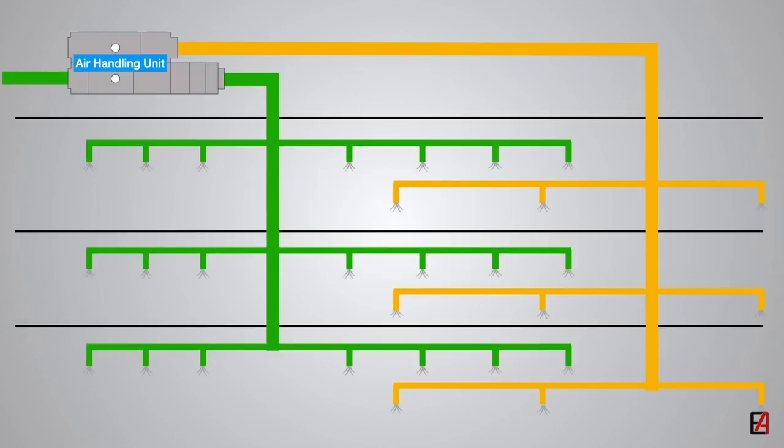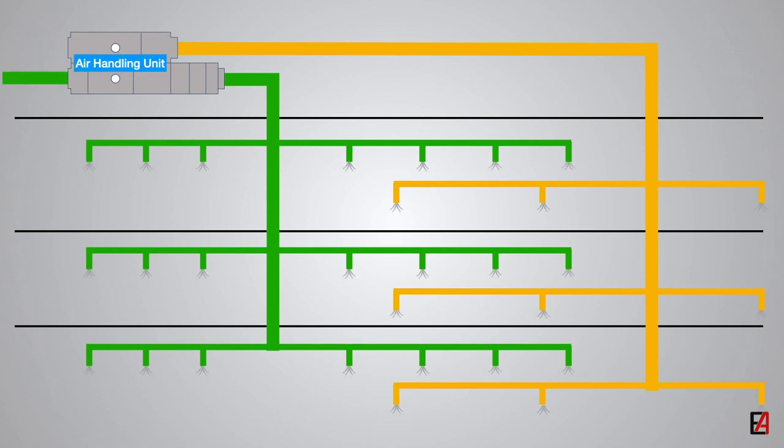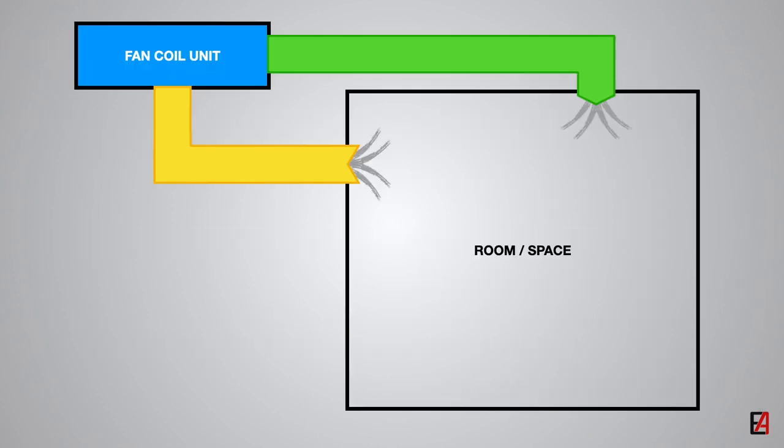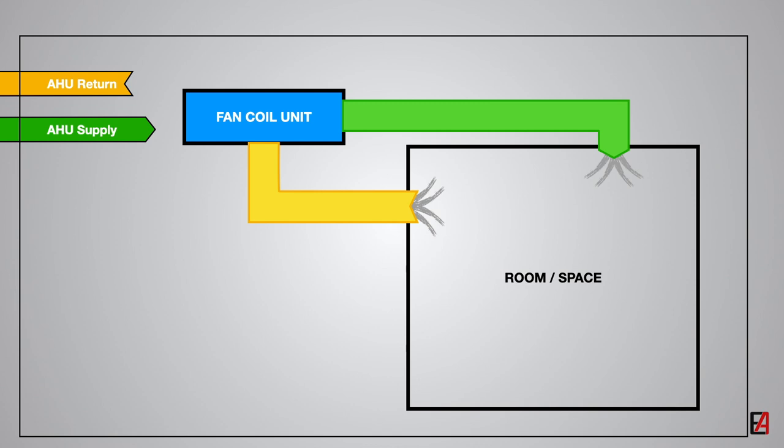Unlike the air handling unit which supplies, circulates, and extracts air from building spaces, the fan coil unit recirculates the internal air from the occupied space or room. In most cases, fresh air to the fan coil unit is supplied by an AHU. The fan coil unit then recirculates it inside the space.